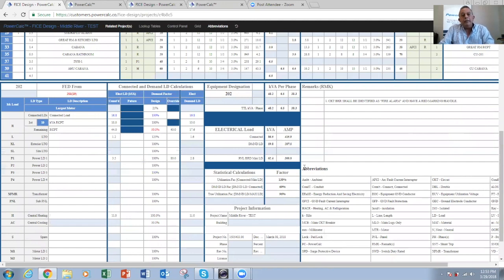So the key point here to apply the demand load is that you have to separate the load based on the NEC load type, which is lighting and receptacles, and then, I'm sorry, the AC and the motor loads, okay? Now the AC, because you have a heating cycle and a cooling cycle, you can demand these separately depending on the largest of the two. And then you can go ahead and take that particular load off the system, kind of thing.